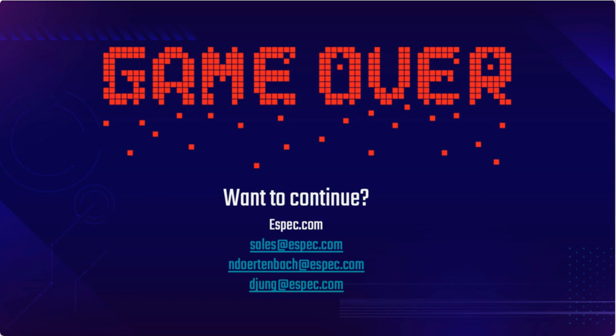Okay, moving along. Looks like we have a question from the audience for Dave. We're in a rented building. How much performance can we get with a chamber just running on electricity? Dave? Yeah, that's a good question. Covered that a little in the presentation, that we have some models that can do different things. What we see most people doing, the chamber I showed was the BTZ 4200, which is 15 degrees per minute, and that just runs straight off electricity. And that's going to allow you to get the adjusted ramps. You don't have to do 15. You can do anywhere up to 15 degrees per minute.